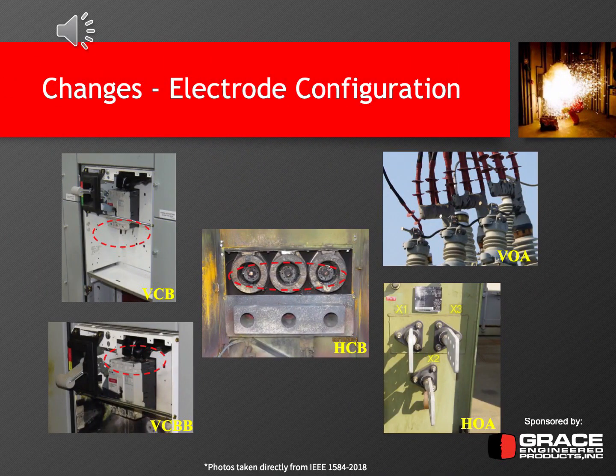So we just saw the pictorial diagrams, or the cartoon diagrams, that are presented in IEEE 1584. But what do these installations really look like in the field? If you look at the top left photograph, that is a VCB installation, and it's highlighted by the red circle. That's the load side of a circuit breaker, where the cables terminate into it on the bottom side, and there's no barrier right at that connection point.